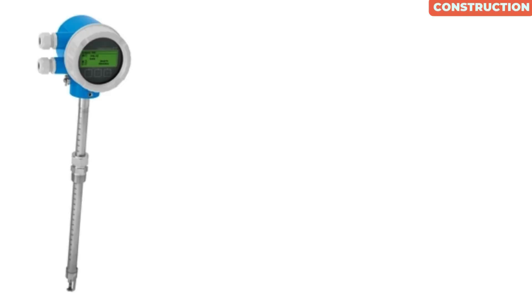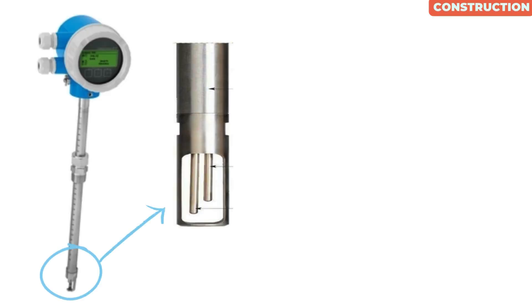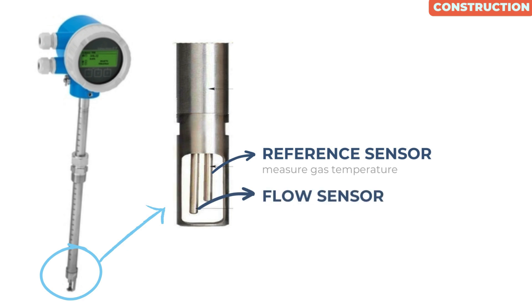Construction of thermal mass flow meter: Toward the tip of the meter's probe there are two sensors available. First, a reference sensor which is used to measure the gas temperature. Secondly, a flow sensor, also known as heated probe, which is self-heated by an integrated circuit.